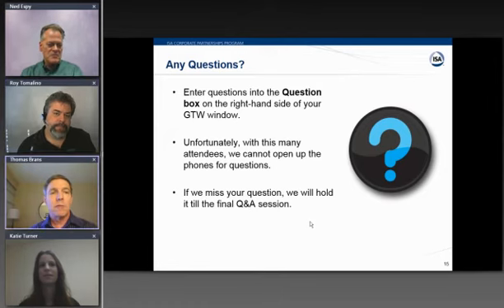I can. Go ahead, Tom. Yeah, I can speak a little bit to the RTD. This is really prior to using an RTD that you'd go through this, but RTDs are pretty linear, but they're not perfectly linear, and that's because of variations in the purities of the platinum that go into making them. And since they're not perfectly linear, the manufacturer can actually do a linearization before, during the manufacturing process. The constants that result from that are called Callendar-Van Dusen constants.